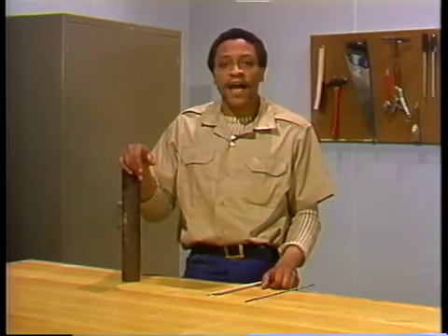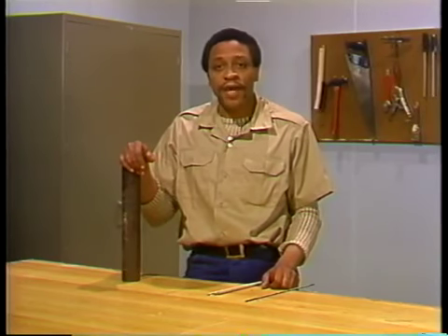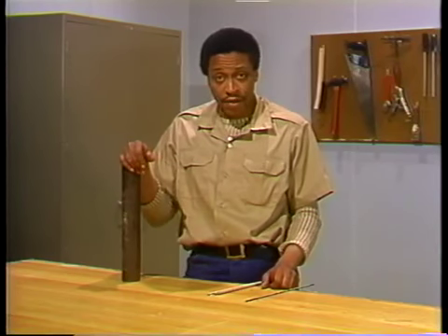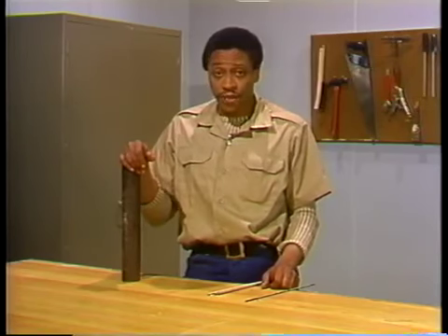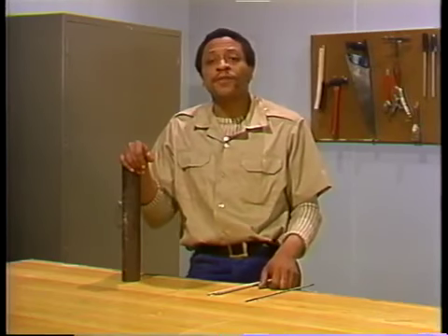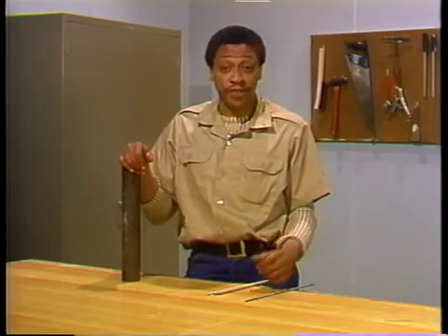The first method of tube repair is the replacement of a section of tube. Here, the length of tube containing a failure is cut out completely and replaced by a new section of tube. Replacement of an entire tube section can be done to repair any kind of tube failure. Replaced tubes are as good as new ones. You can replace every tube in the boiler, or as much of one tube as necessary.